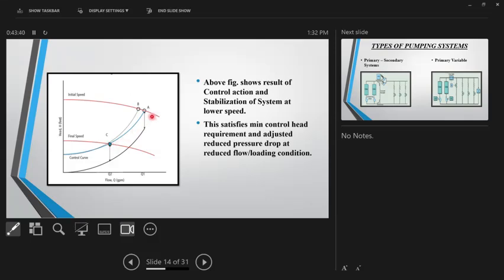Let me repeat again, carefully. The final speed is a speed where you are satisfying the reduced flow, let's say Q2, and this distance is equal to this distance. Whenever these two conditions are met, that's the final speed point. So the above figure shows the result of control action and stabilization of the system at lower speed. This satisfies the minimum control head requirement. It is set to a reduced pressure drop at reduced flow and loading conditions. So this is the theory: when you say the VFD reduces the speed to respond to the load, actually this happens in the background.